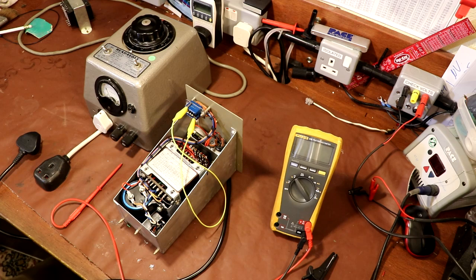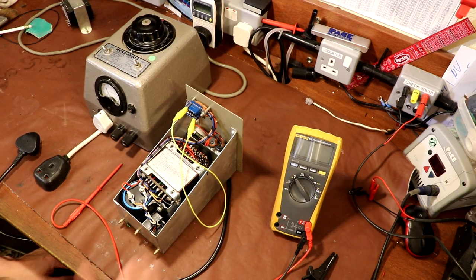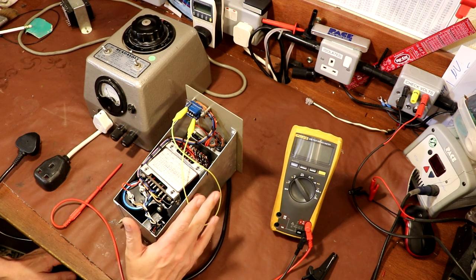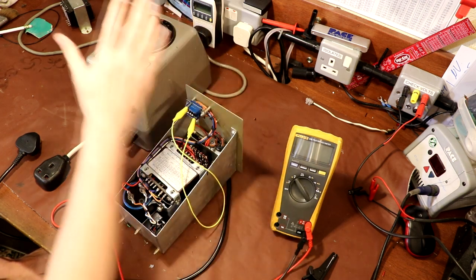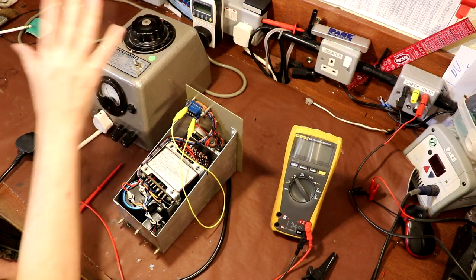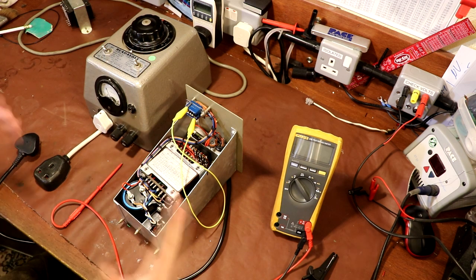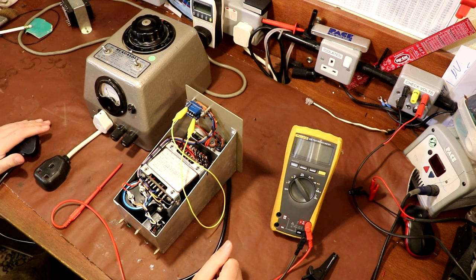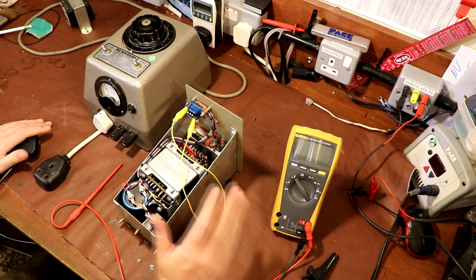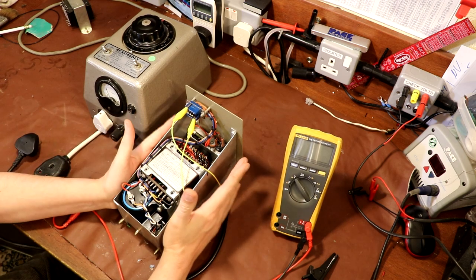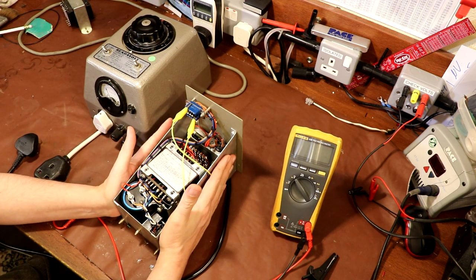Oh, and I've tripped the power out. Well, how queer - I don't know if you noticed, all my power just tripped out then. What I'd actually done is taken this power supply off the isolation transformer and plugged it onto this variac, which is non-isolating, and the main earth leakage circuit breaker just tripped out in my consumer unit. So really that's implying we've got a fault to earth within this power supply.